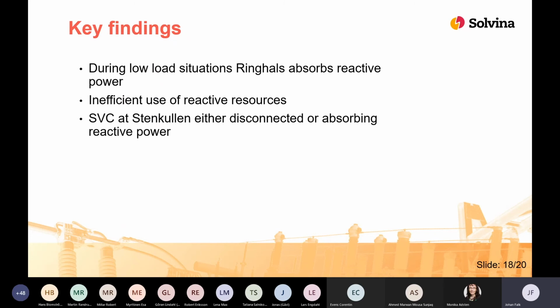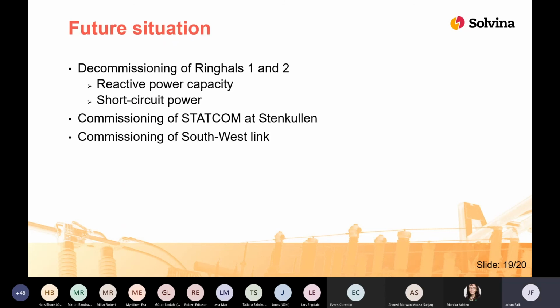This might not be the most efficient use of the SVC. However, now it's decommissioned, so yeah, the StatCom might change things. And now some of the three main things that we have highlighted in the report that may influence these aspects in the future. The decommissioning of Ringhals 1 and 2 will of course lead to a reduction in reactive power capability in the region. This may be up to 600 megawatts for both Ringhals 1 and 2.